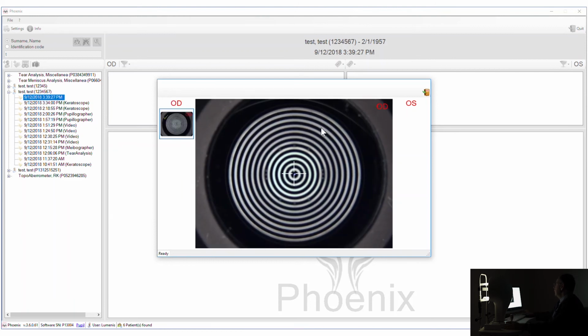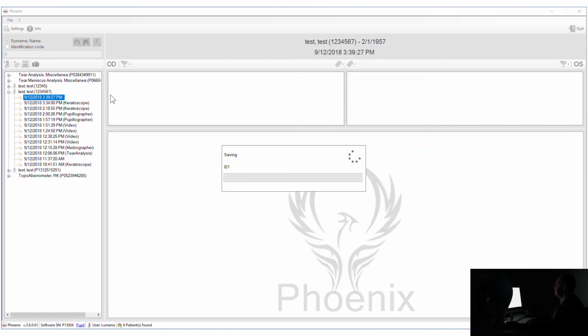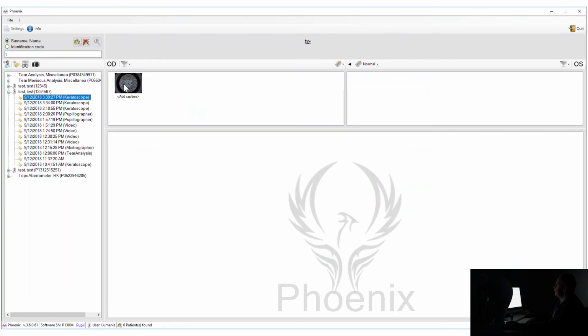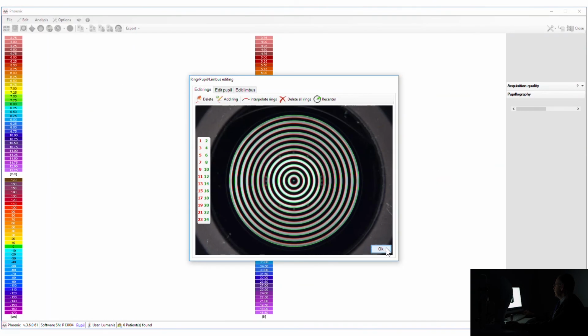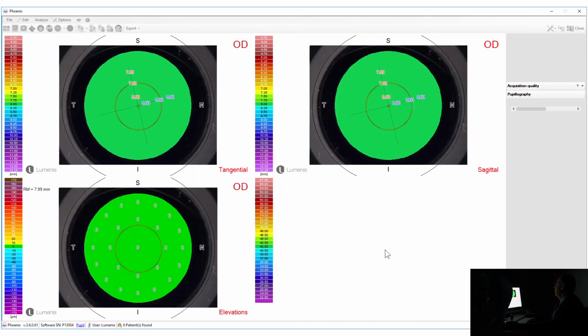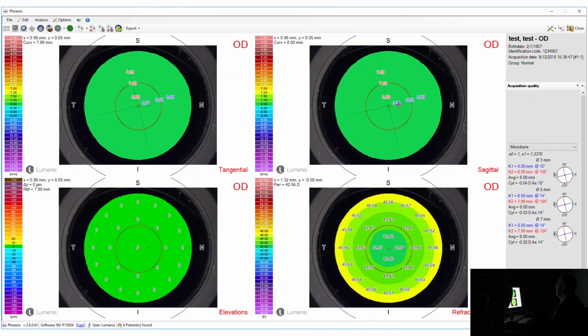So we've redone the test as such. We will get the answer in a second. And we have 8.00, 7.99, 7.99. So that proves that the calibration was done successfully. We can see on the heights that there are no differences in the heights. They're all zeros. We're talking about microns here. So that's a very good, successful calibration. So we're really happy with that.